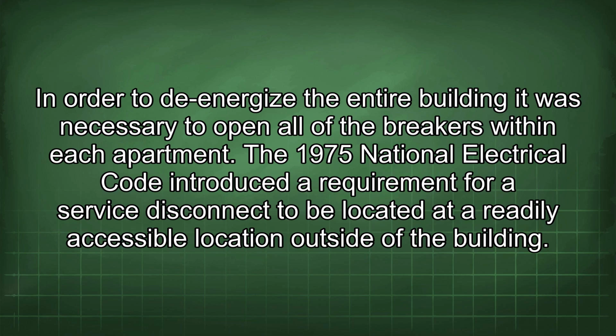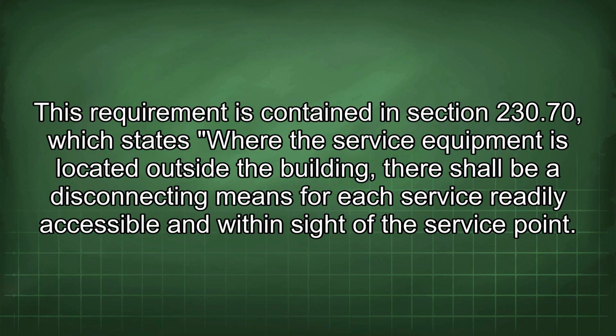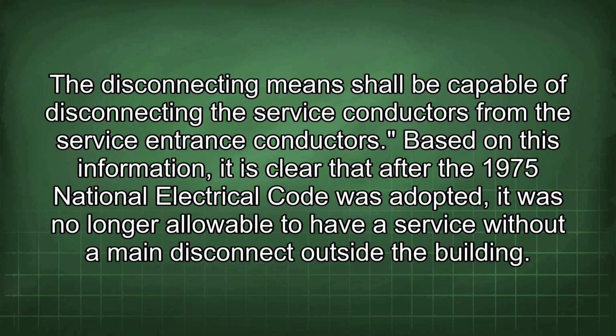The 1975 National Electrical Code introduced a requirement for a service disconnect to be located at a readily accessible location outside of the building. This requirement is contained in Section 230.70, which states where the service equipment is located outside the building, there shall be a disconnecting means for each service readily accessible and within sight of the service point. The disconnecting means shall be capable of disconnecting the service conductors from the service entrance conductors.